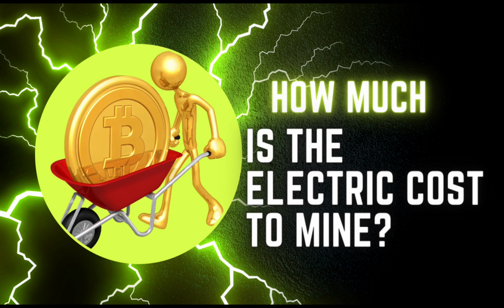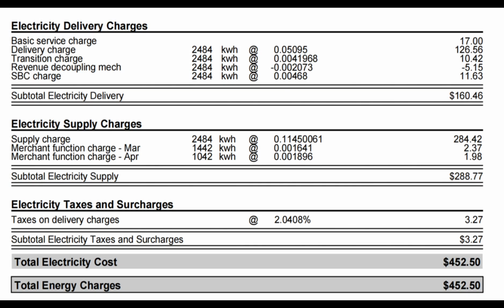When figuring out the cost of electricity, make sure you are reading the electric bills. In this sample electric bill breakdown, we see the cost of delivery fee on top of supply fee, and the delivery fee alone is already almost 6 cents per kilowatt, about 50% of the 11.6 cents for the cost of electricity itself. This means the actual cost of electricity is about 17.5 cents per kilowatt hour, even though the utility company says they only charge 11.6 cents per kilowatt hour.